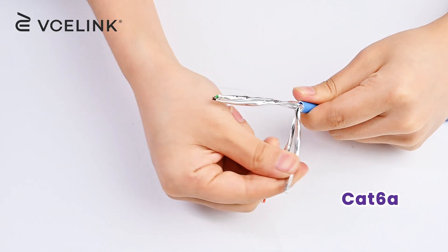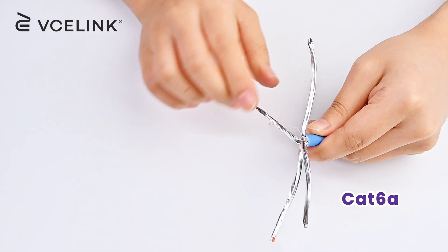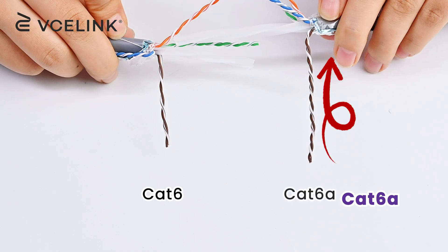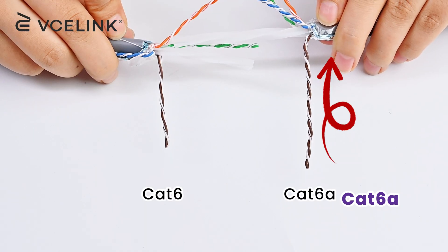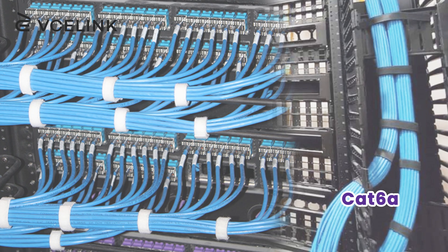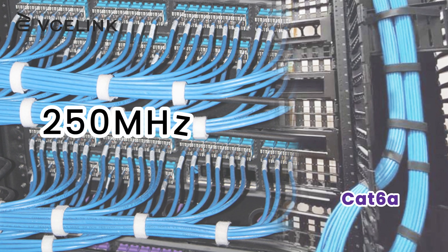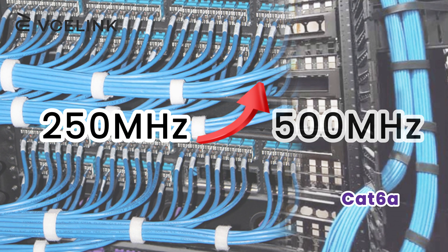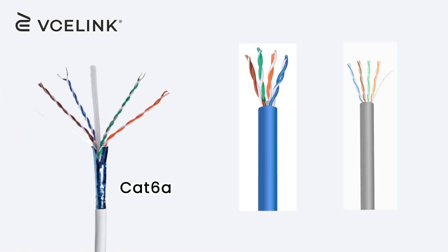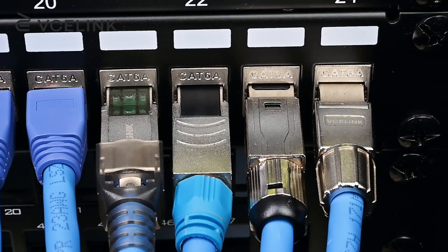CAT 6A Ethernet cables mean the augmented CAT 6 cables. The CAT 6A cable often consists of tighter twisted pairs compared to CAT 6 cables to avoid crosstalk interference. It has a transmission bandwidth ranging from 250 MHz up to 500 MHz frequency. CAT 6A Ethernet cables are backward compatible with CAT 6 and CAT 5E connectors, keystone jacks, and so on.